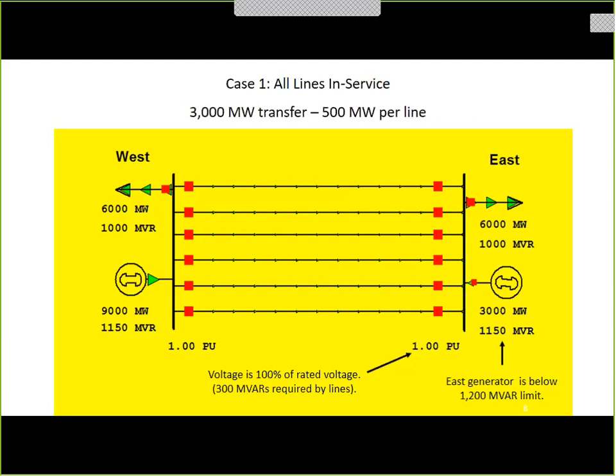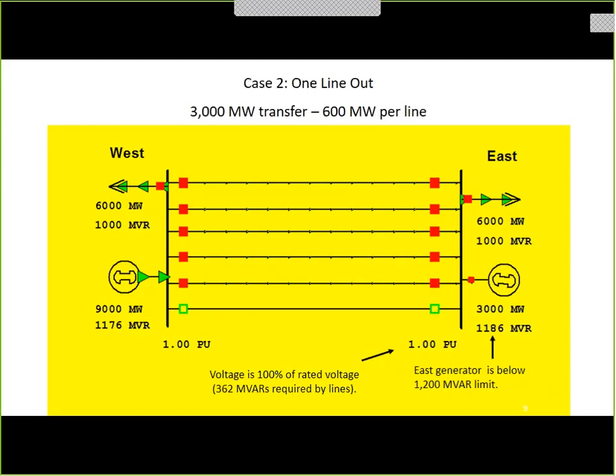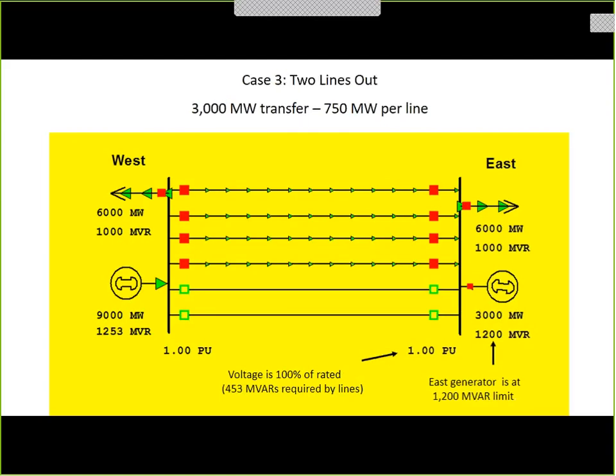They're inductive components. Okay, take out one line. That 500 megawatts has to go somewhere. Well, it redistributes into the other 5 lines because you're still generating 9,000 and you're still transferring 3,000 over here to the east. But the loading on those lines went up from 500 to 600. The VAR requirement here in the east went up to 1186. But 1186 is still less than 1200. So the voltage is still 1. So everything's still fine.